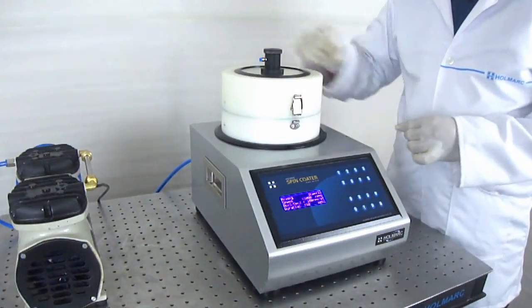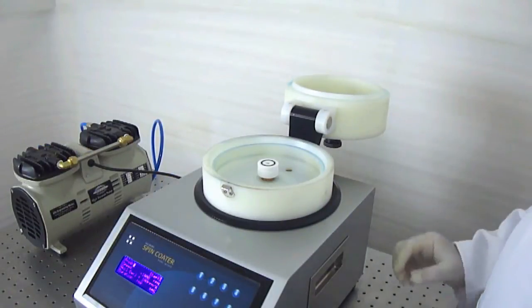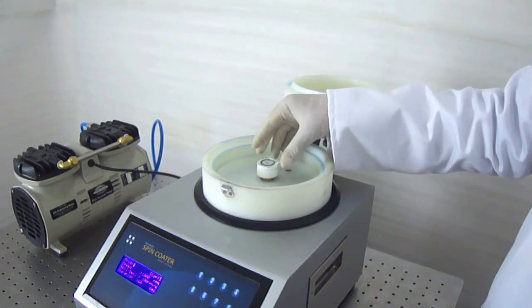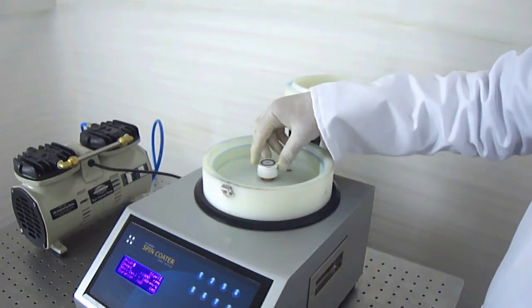The device is equipped with a teflon bowl into which the substrate to be coated is placed. The substrate is held in place using vacuum. The spin head is provided with vacuum chucks for this purpose.